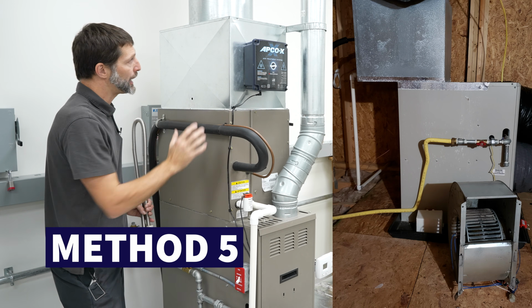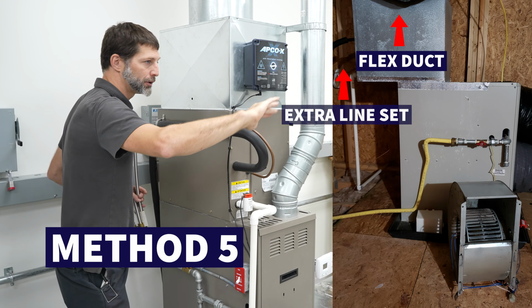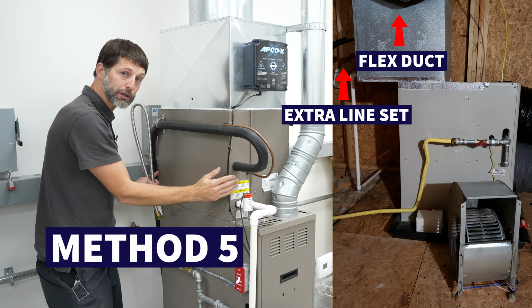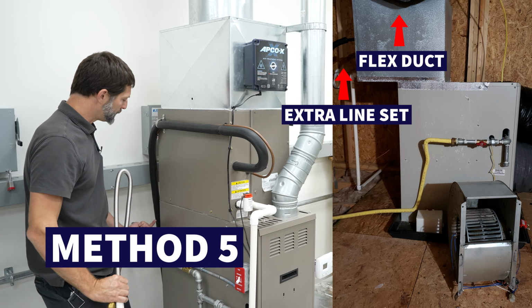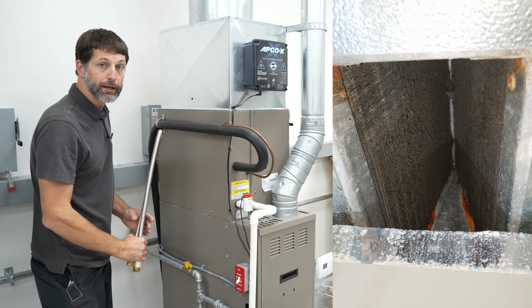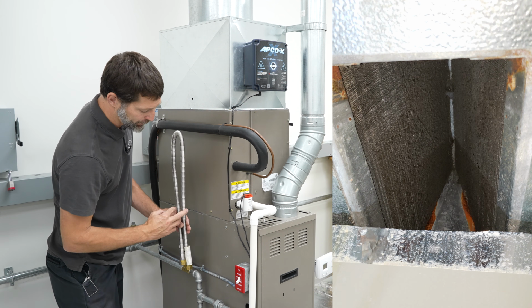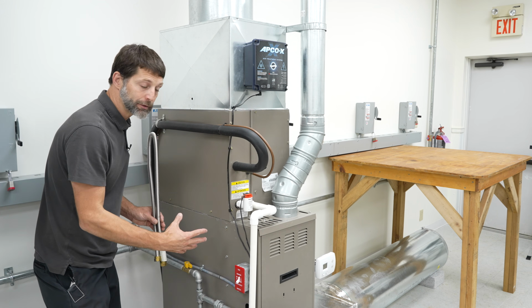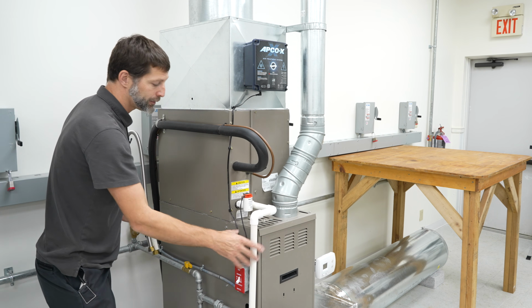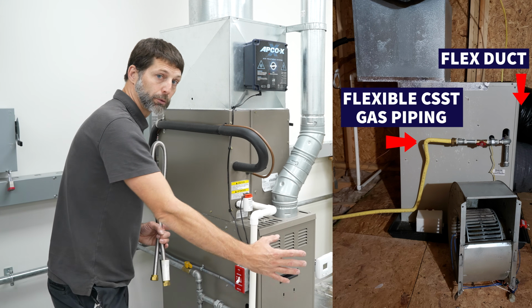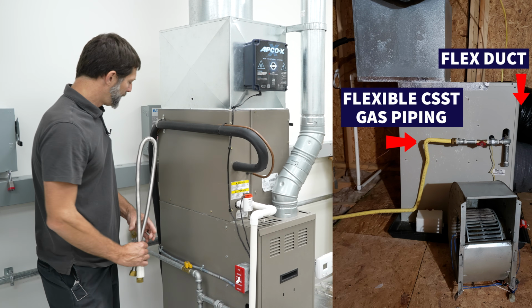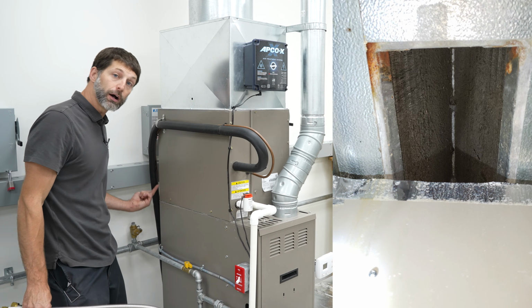Method number 5 is if you happen to have a flex duct and maybe a little extra line set length, it may be possible to shift this coil back, and that would expose the underside of the coil. And likewise, if you have a flex line or a union on the gas line and maybe B vent on your gas furnace, it may be possible to slide this forward with the power off and the gas off, and thereby exposing the underside of the coil.